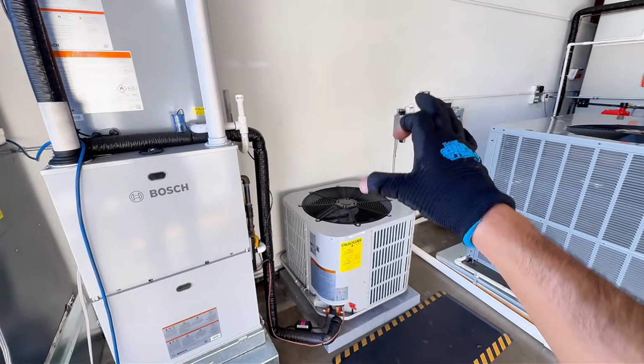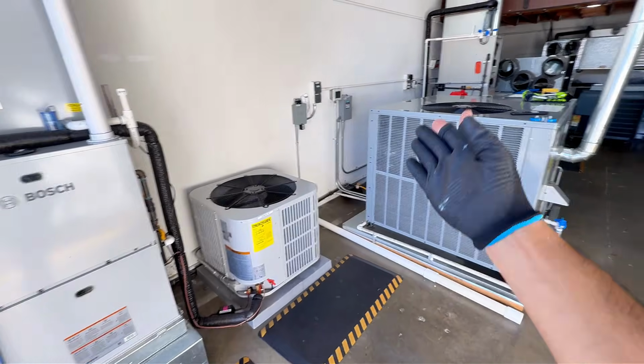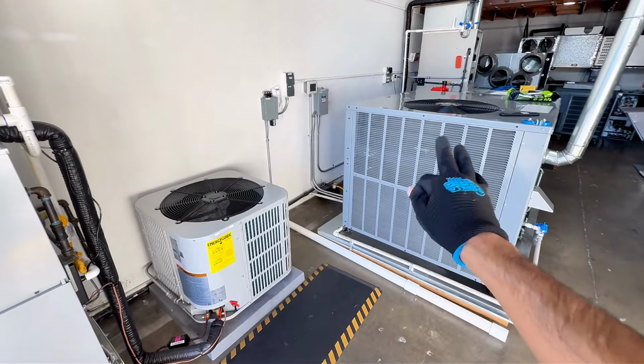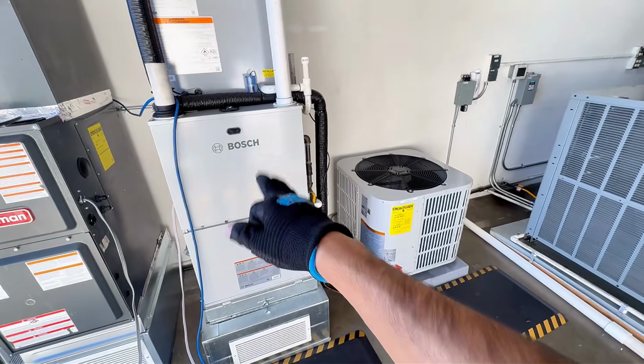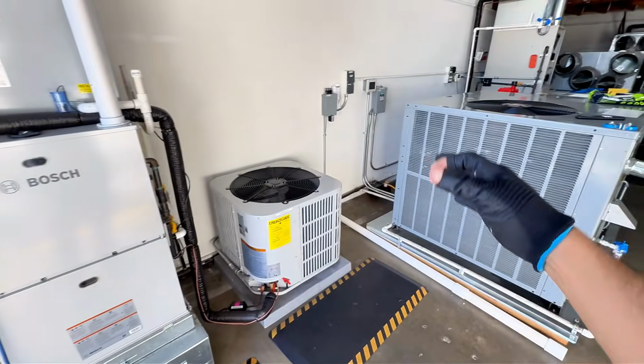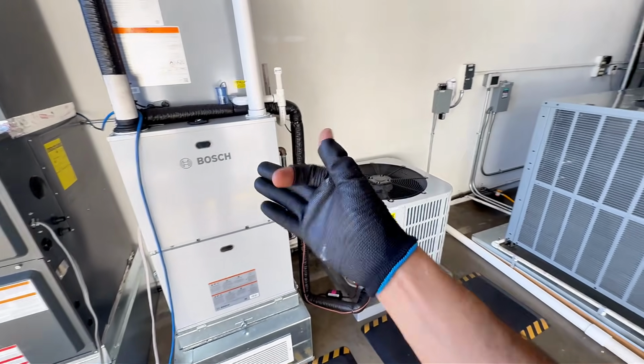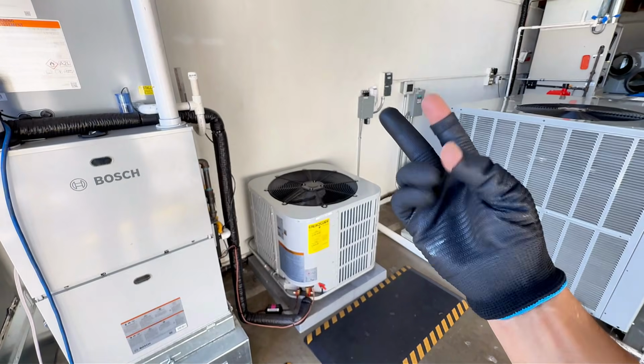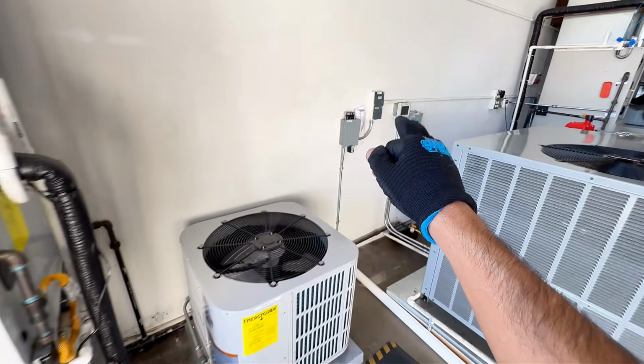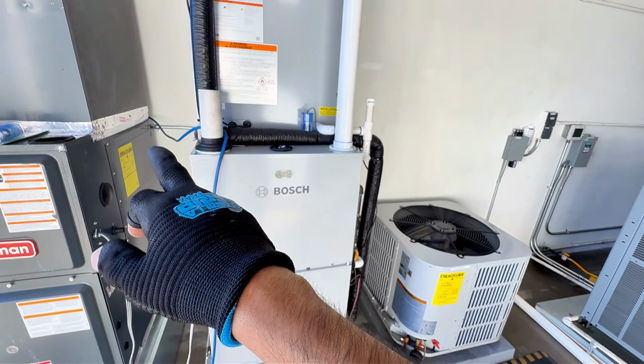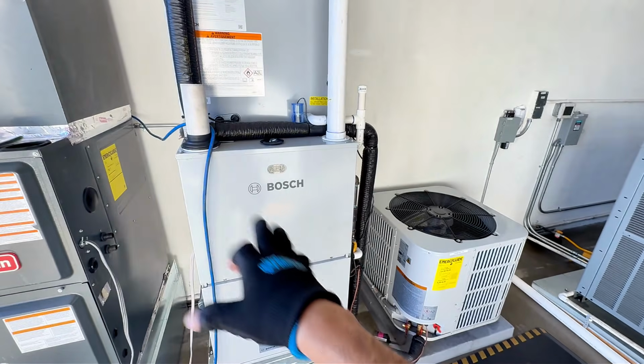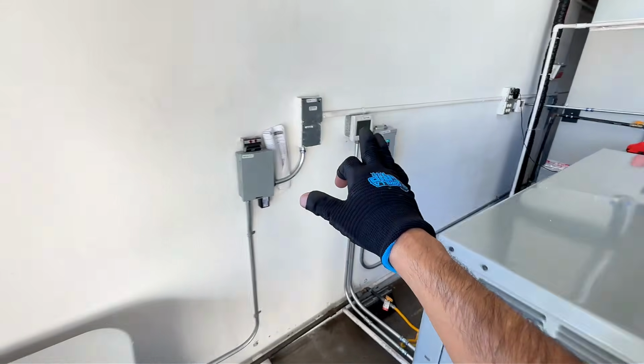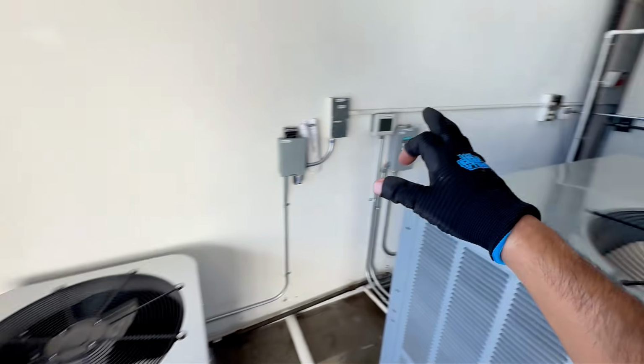All right, the second question is, how do we set up the thermostat so we can get stage 2? In this specific example, this one has second stage cooling, and this one has second stage heating. But if you don't set it up on the thermostat, you will always be on stage 1 cooling and stage 1 heating. You actually have to tell the thermostat that it has 2 stages and set it up when to call for second stage. So for this one, I'm gonna do it on this thermostat because this thermostat has a stage 2 capability. We currently are working on getting a thermostat that has stage 2 right now. Right now, we're just running it on stage 1.